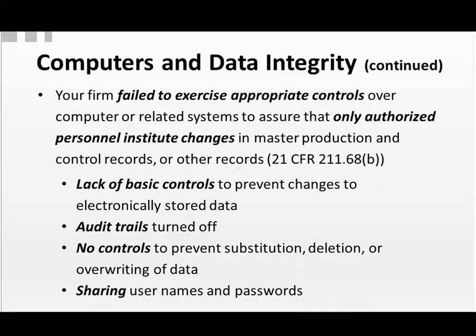In this case, a firm failed to exercise appropriate controls over their computerized systems. They didn't ensure that only authorized personnel made changes in a master production and control set of records or other records. That lack of basic controls to prevent changes to electronically stored data is going to cause you to have a finding from FDA.